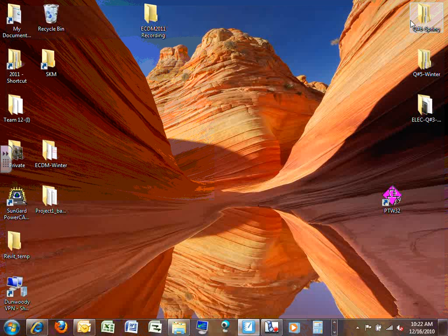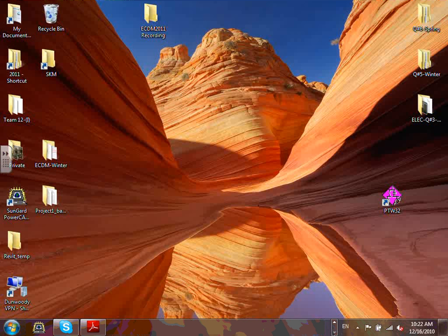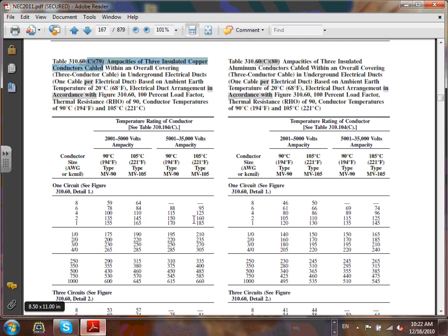When the voltage is higher than 600, I said this one time, and there was a guy in one of my classes, and he said, Chad, what would I do if my voltage, he has a machine that his voltage is 750. 750, very weird machine. If you guys look at 310.16, it says up to 2000 volts. So in reality, up to 2000 volts you can use. If you look at 310.16, it says 0 to 2000 volts. So any system 0 to 2000 volts is covered by 310.16.